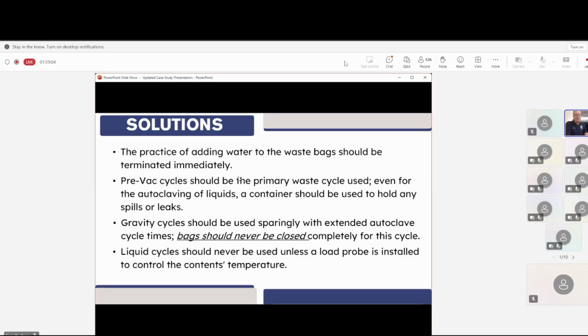So the practice of adding water, I think the dangers outweigh the adding liquids to the effectiveness of it. It's not going to make that much difference, but it can cause you problems. Pre-vac cycles, obviously they're the ones, that's the jackhammer as opposed to the tap hammer. Gravity cycles, if you're going to use them, if you don't have it, make sure that you know that you need to extend the time, especially depending on the loads and the density of the loads. Try to open the bags as much as you can. If you close the bag on a gravity, you might as well just assume you're not going to get the kill.